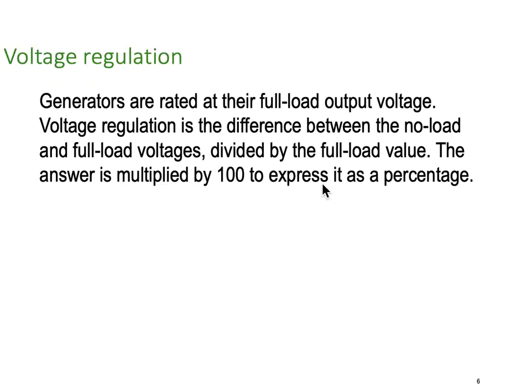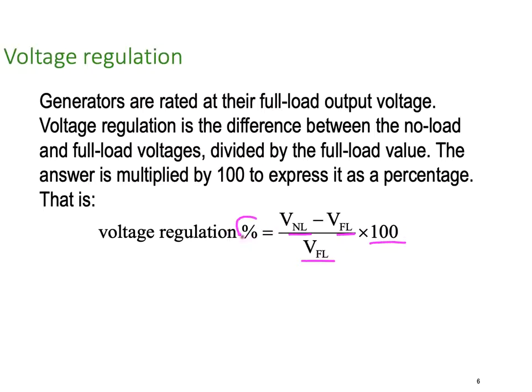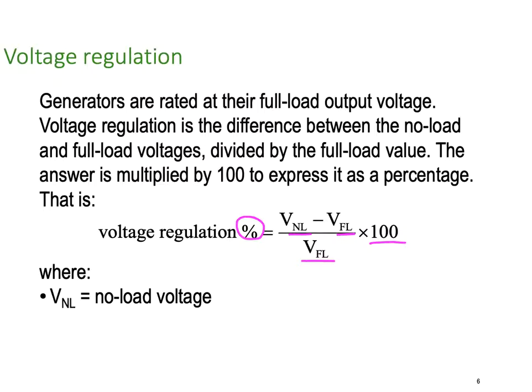Generators are rated at their full load output voltage. Voltage regulation is the difference between no load and full load voltages divided by the full load value, expressed as a percentage. The formula is: percent voltage regulation equals VNL minus VFL, multiplied by 100, all divided by VFL. NL is no load, FL is full load.